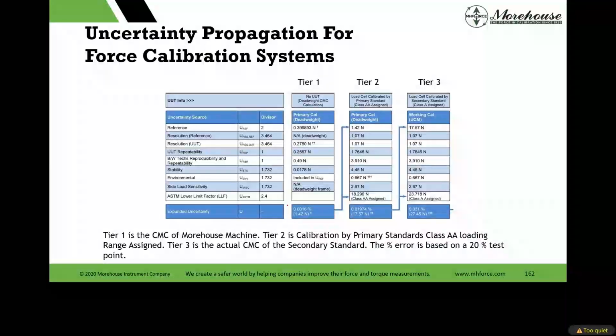This is how uncertainty starts to look. I dead weight calibrated, adjusted, did all this. This is a 120K machine. All the weights were calibrated by NIST. They were adjusted in. NIST is awesome. They're expensive, but they're well worth it. You get what you pay for on that one.